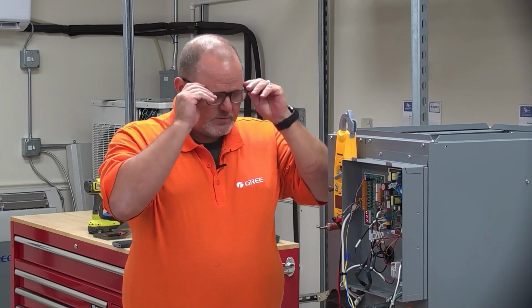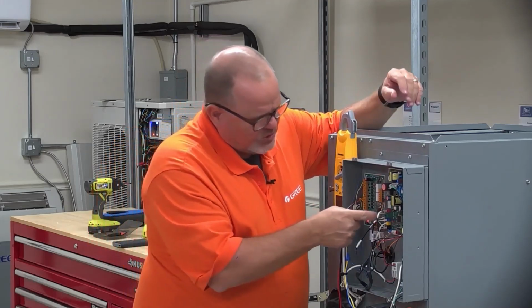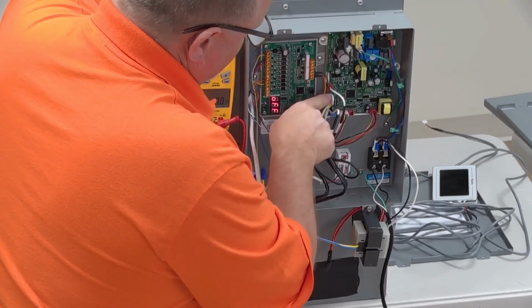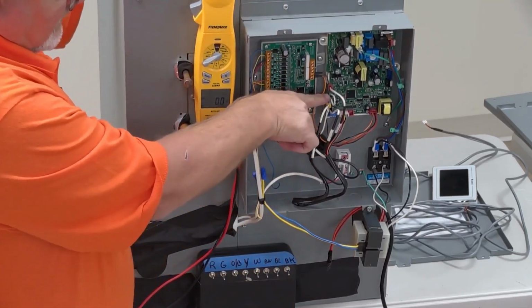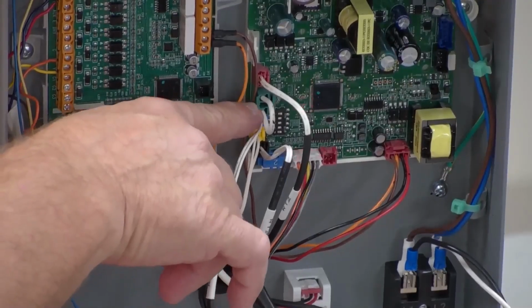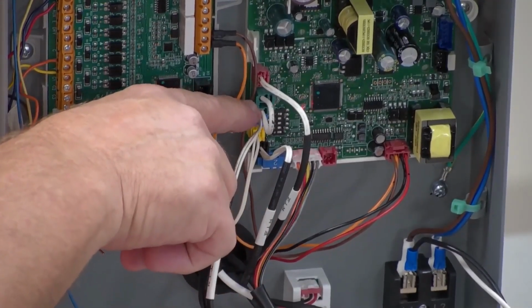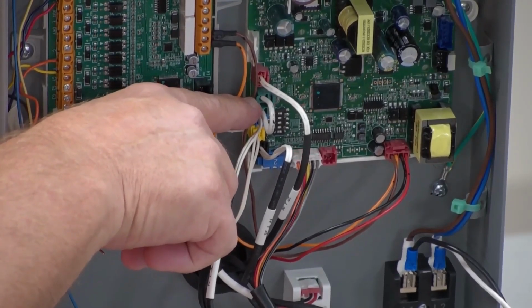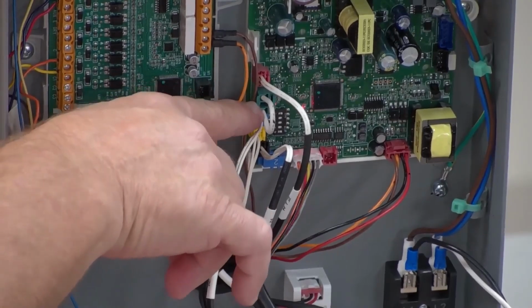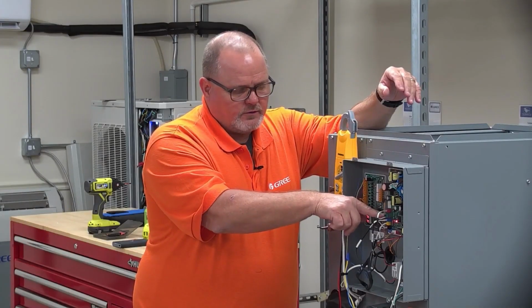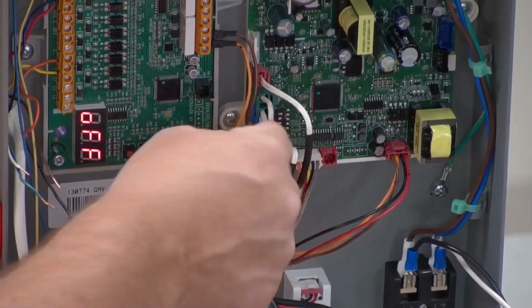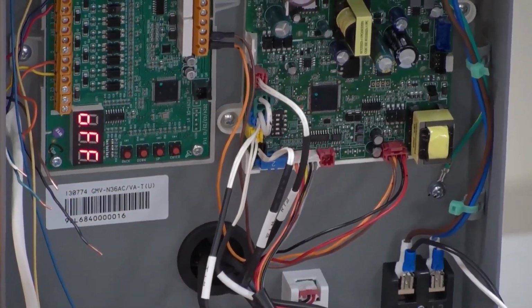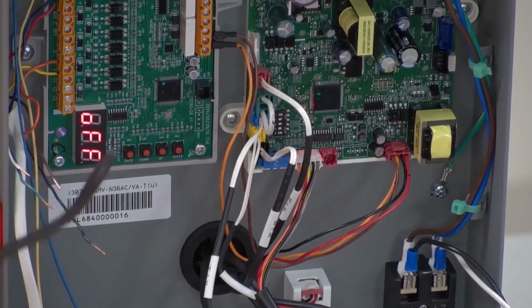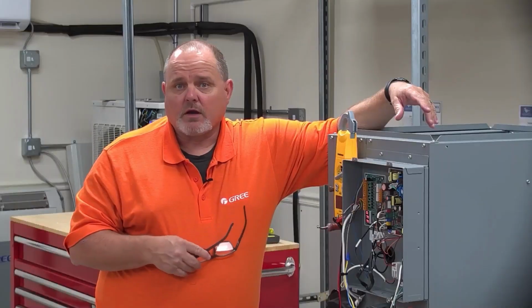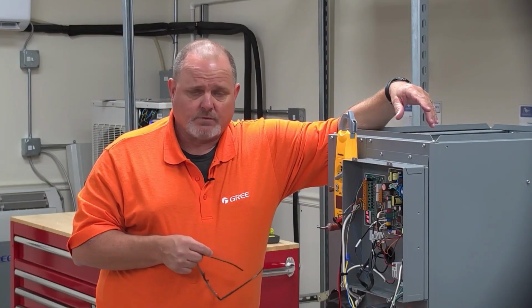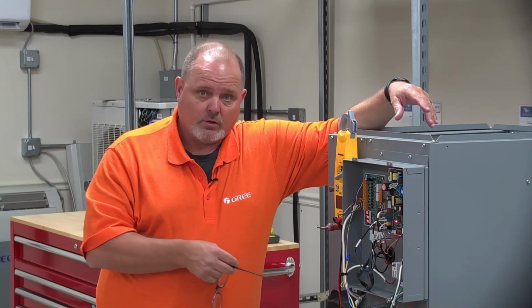So one other thing, a couple other things to point out here, I guess. This little green jumper right here, or green plug with the white jumper, that is your condensate overflow switch. It comes jumped out from the factory. If you're going to put a float switch on the condensate drain or emergency flow pan or whatever you're doing there, all you got to do is unplug this and then just cut the jumper, wire one side of your float to one side of that jumper, the other side of the float to the other side of the jumper, plug it back in. It will actually give you an L3 error code if for some reason your condensate float is tripped, and it won't allow the heat pump to run in cooling mode.